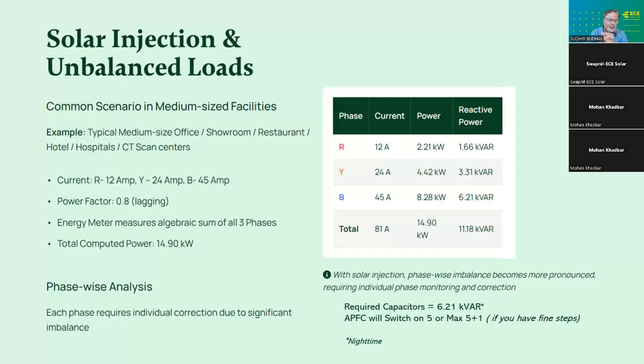So let's take an extreme example. Say the current in R phase is 12 amperes, Y is 24 amperes, B is 45 amperes. Extreme example. Okay, so let's plot it, see a chart. Current is 12, my power is 2.21, then Y phase is 4.42 and B phase is 8.28. What happens to billing? We have seen in the initial part that the energy meter takes an algebraic sum of all three phases. So it will compute a demand of 14.9, and DISCOM will happily bill at 14.9. They are happy. They have nothing to lose.